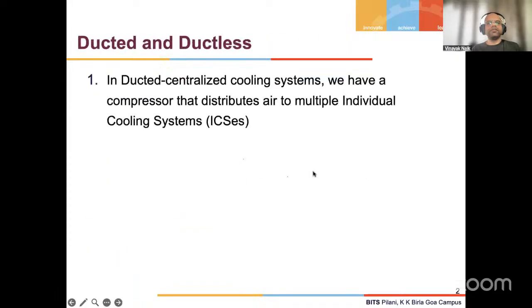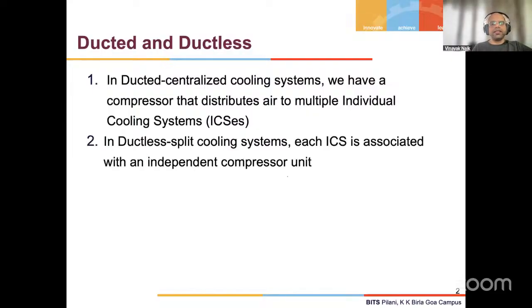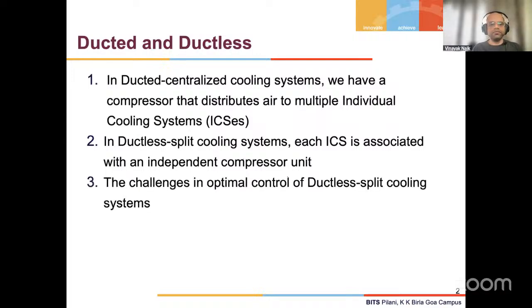Now a few more terms. In a ducted centralized cooling system, a single compressor distributes air to multiple individual cooling systems — the small panel in every room that controls temperature and fan is called an individual cooling system, or ICS. In a ductless split cooling system, each ICS is associated with an independent compressor unit located outside the room.